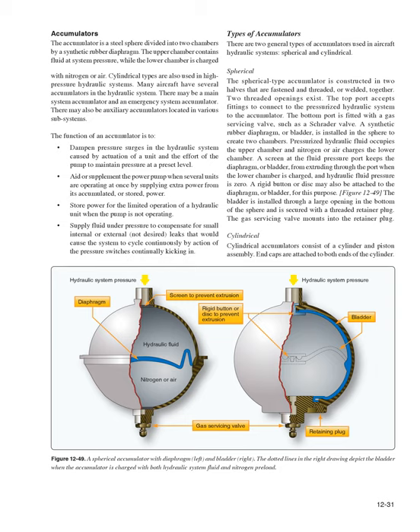A screen at the fluid pressure port keeps the diaphragm, or bladder, from extruding through the port when the lower chamber is charged and hydraulic fluid pressure is zero. A rigid button or disc may also be attached to the diaphragm, or bladder, for this purpose. Figure 12-49: the bladder is installed through a large opening in the bottom of the sphere and is secured with a threaded retainer plug. The gas servicing valve mounts into the retainer plug.